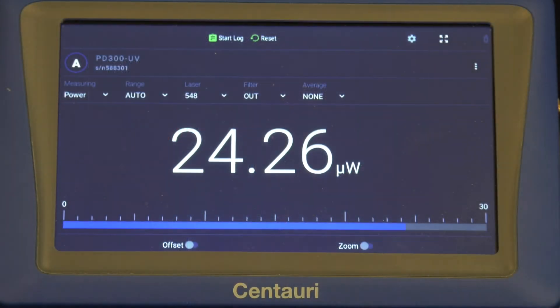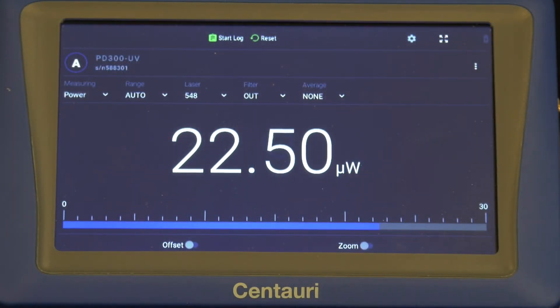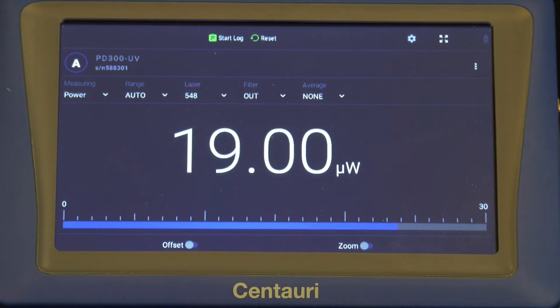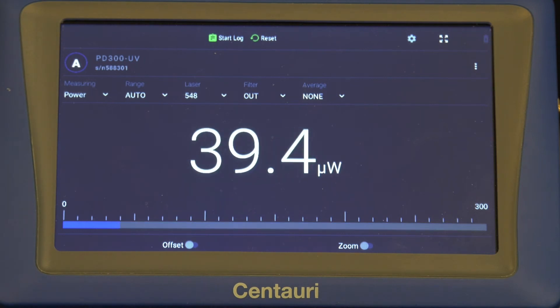So we asked the customer for some actual logged data. From the data log, we saw that the range had been set to auto. When the range is set to auto, it takes the instrument a certain amount of time to find the best range. During those time gaps while switching ranges, there is of course no measurement data. In other words, in auto range, there will very likely be time gaps during which no measurement takes place. If one works in a fixed range setting, this shouldn't happen. In general, it's most likely not a problem once one knows what it is.